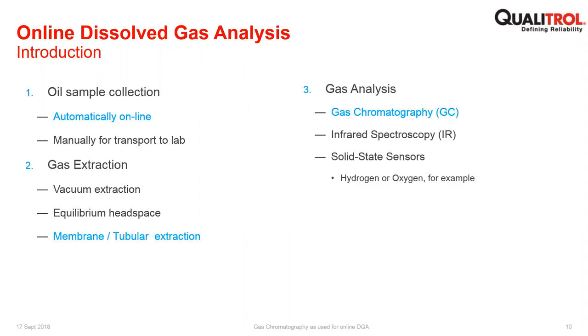The next thing to consider for online DGA is the analysis of that gas. So you've collected the sample, you've extracted the gas out of the sample, and now you're going to analyze it. Gas chromatography is the technique used in the laboratories and the technique used in the Qualitrol products. But infrared spectroscopy can also be used, and there are multiple variants of how infrared spectroscopy is deployed: photoacoustic spectroscopy, NDIR, or non-dispersive infrared, NIR, or near infrared, and others. Or there are solid-state sensors, although generally solid-state sensors are limited to one or two gases and cannot provide the full range of gas measurements.